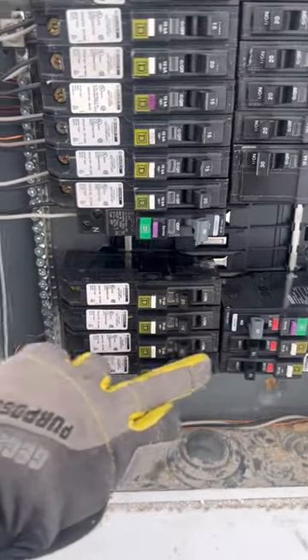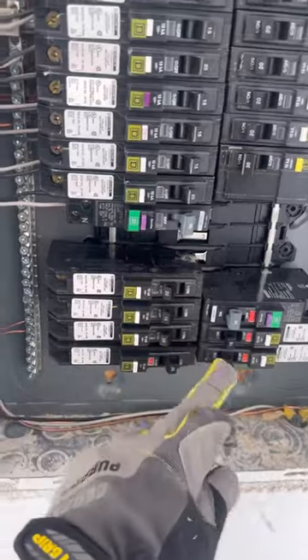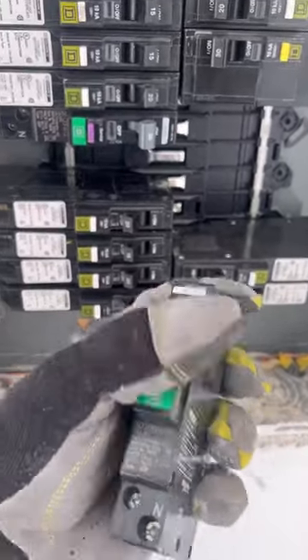The neutral was loose inside the disconnect, causing all that fault current not to return to its source. Instead, it was going back through the ground rod and into the Ufer ground in the garage that is connected to the slab.